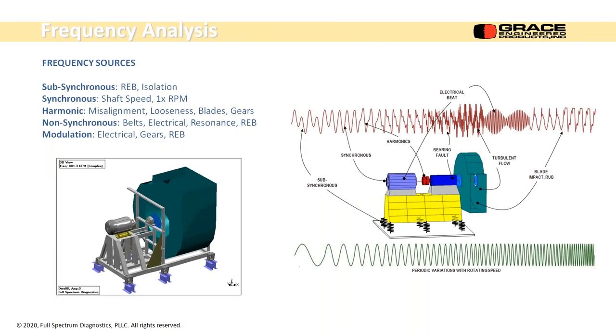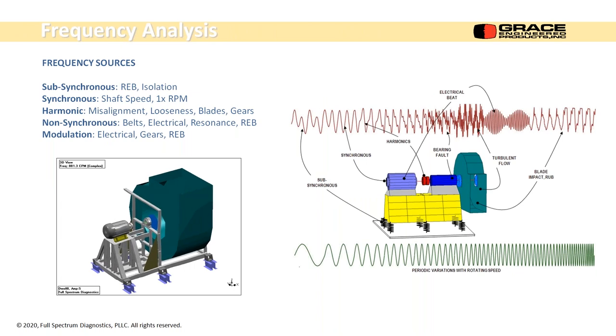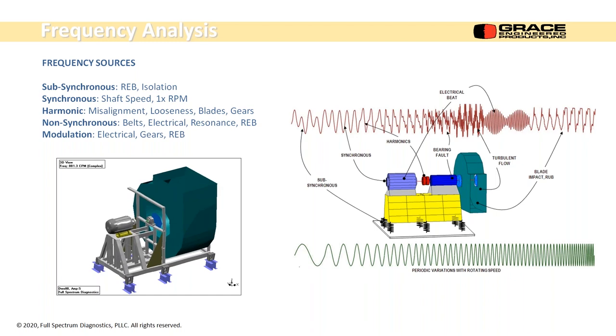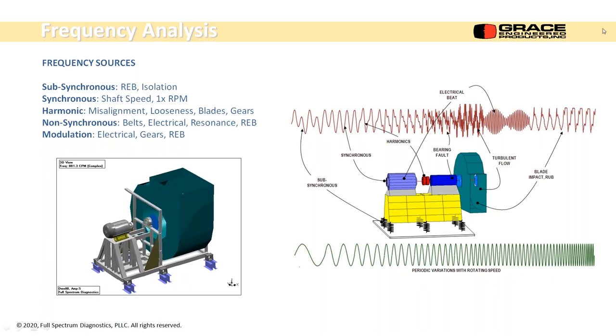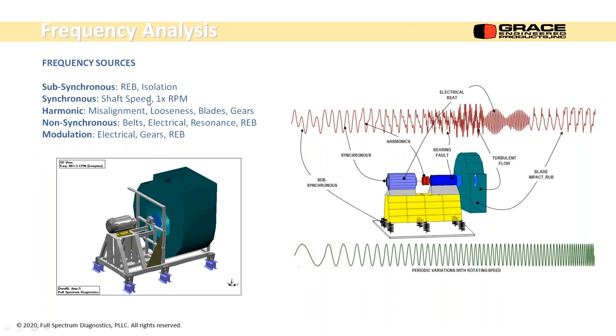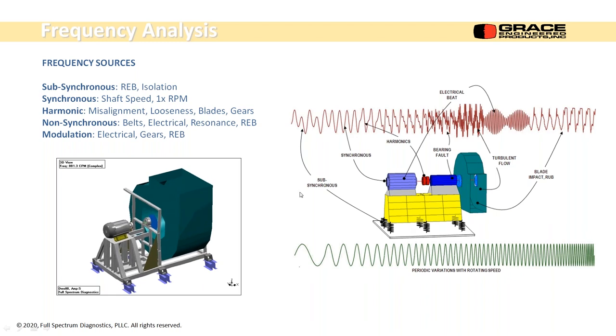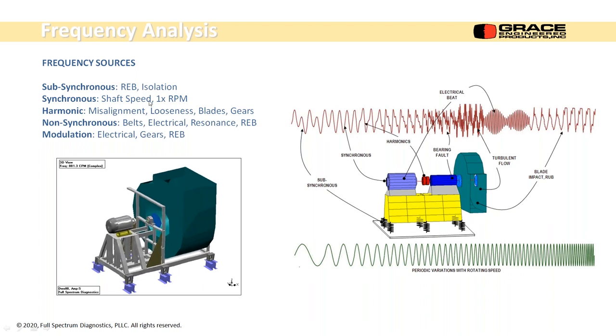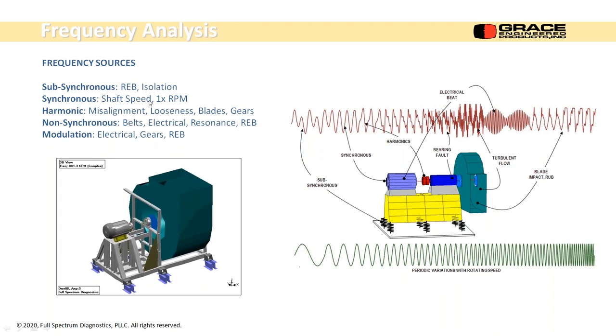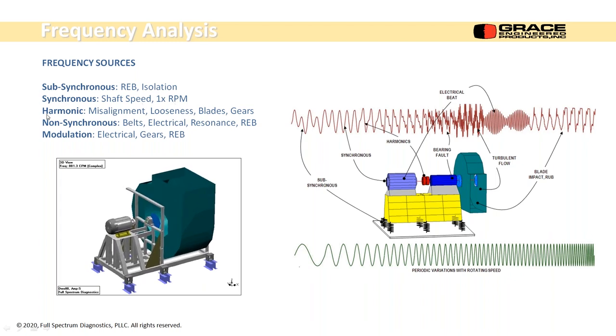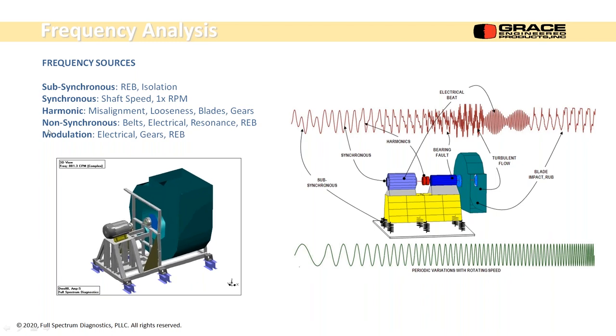There's a lot of sources. And when you think about it, I have a direct coupled center hung fan and overhung fan over here, but same deal. Subsynchronous frequencies, the rolling element bearings can cause subsynchronous. The isolation system, the springs that the structure's on, can bounce and cause a low frequency vibration that's subsynchronous. Synchronous is shaft speed, turning speed of the shaft. Harmonics are from misalignment, looseness, blades, and gears.